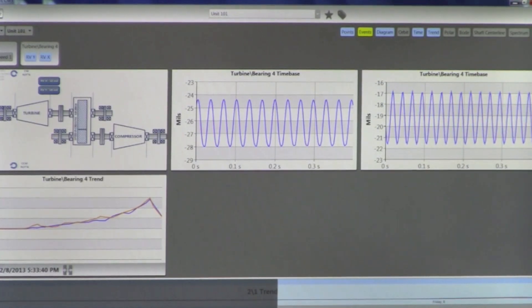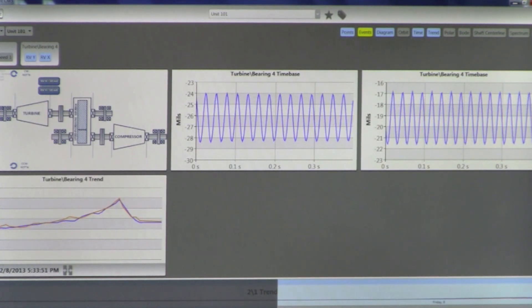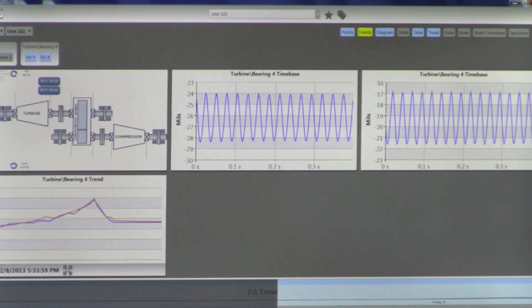Once the waveforms are stored in the Pi Historian, we can run an FFT on them, so we can do full spectral, cascade, and waterfall kind of presentations. We can take the two waveforms, display them in an XY format, and show an orbit. We have some of the best historian tools to manage this data and to be able to display it over time.